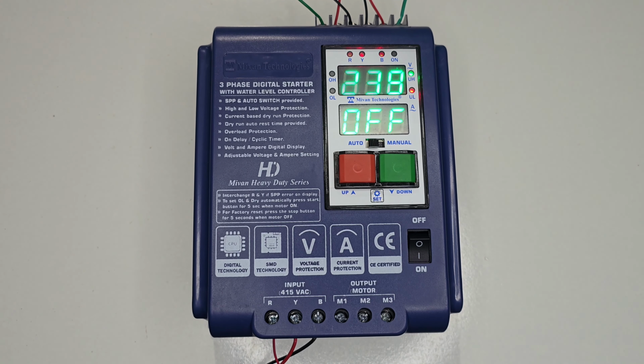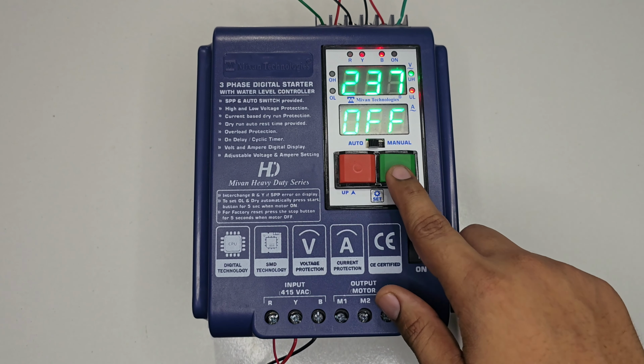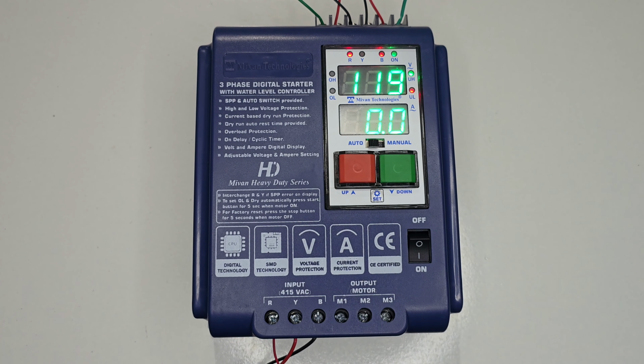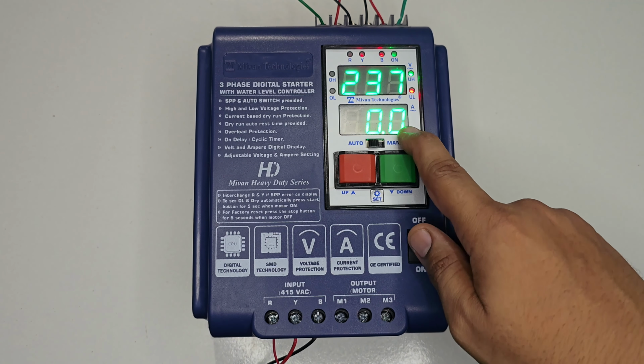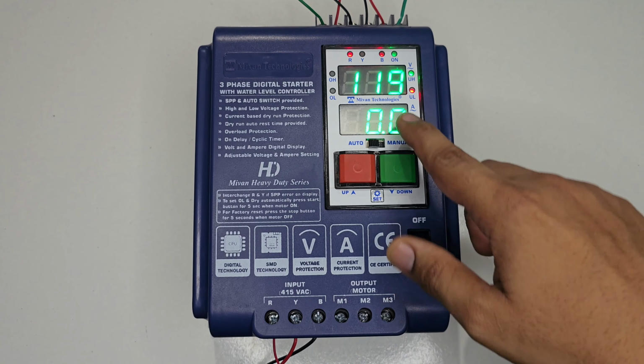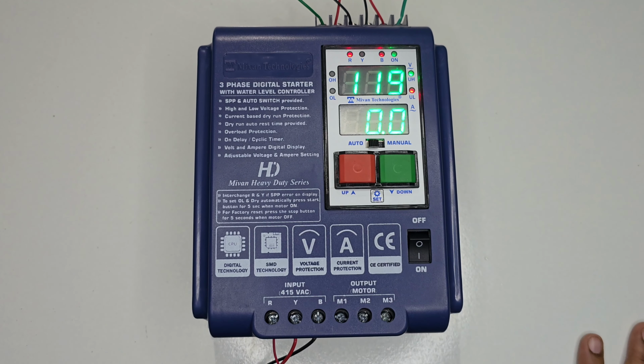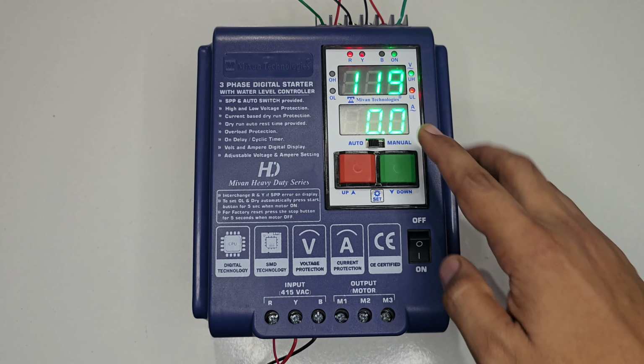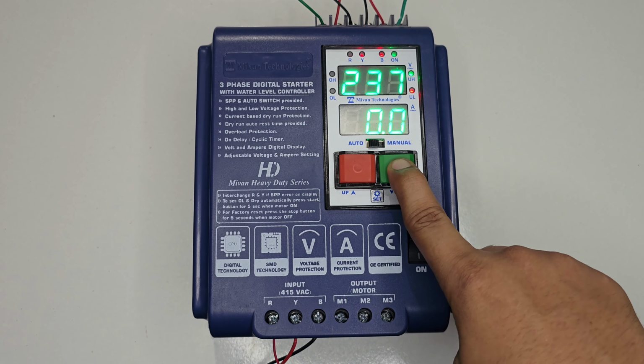Now I'll show you how to set the overload and dry current automatically. To set the overload and dry current automatically, first press the set button and start the motor. Once the motor gets started, wait for a minute for the ampere to get stable. Here I have not connected a load, so it's showing 0 ampere. Once the ampere gets stable, press the green button for 5 seconds.